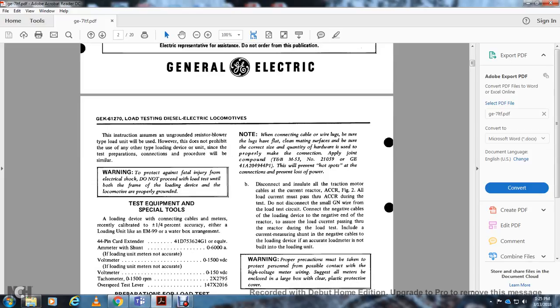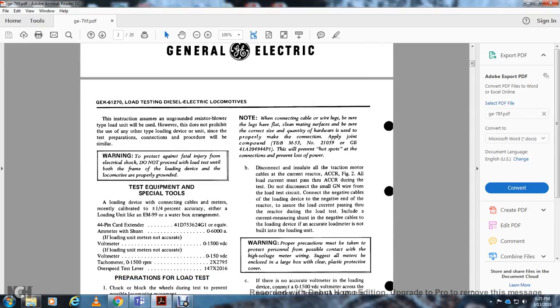The instruction assumes that a resistor type of load will be used. However, this does not prohibit the use of any other type of loading device, and the testing preparation and connection procedure will be similar. Warning: to protect against fatal injury from electrical shock, do not proceed with the load test unless both the frame of the loading device and the locomotive are properly grounded. Test the equipment and special tools.